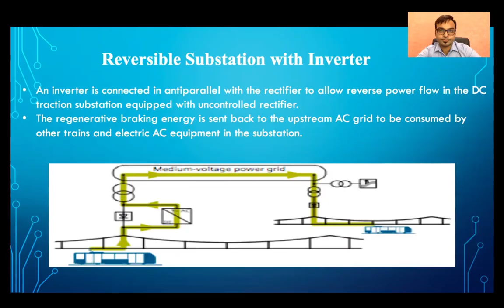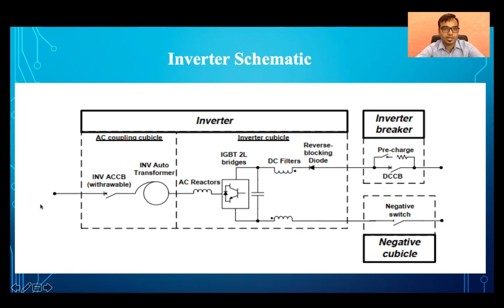In Kanpur Metro, we are using an inverter with auto transformer. The DC energy is fed to the inverter through an inverter breaker and a negative switch available in the negative cubicle. The inverter cubicle has IGBT bridges to convert DC energy into AC, along with DC filters and AC reactors to improve power quality. In the AC coupling cubicle, the inverter auto transformer is placed, which ensures the required voltage level before being connected to the medium voltage network.